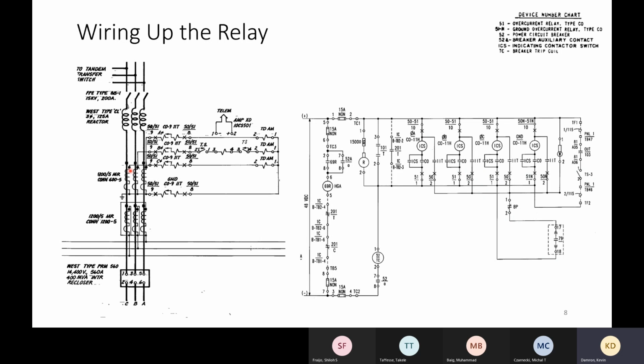Because if there's communications, it gets included as well. So a number of things go into it. But if we look here, we've got any particular phase. We follow this up. Here's my A phase. So here's my A phase relay. It goes through terminals 9 and 8 on the CO9 relay, so it goes through both the time overcurrent and the instantaneous. It comes over here, goes through a meter.